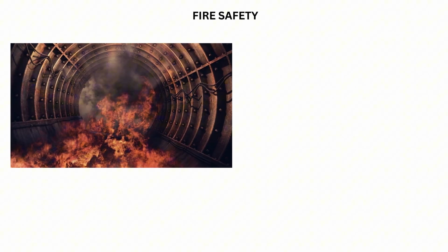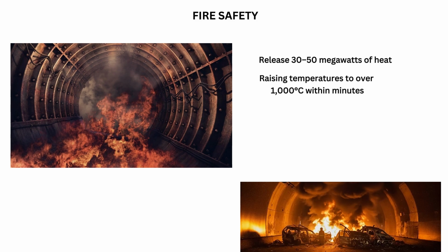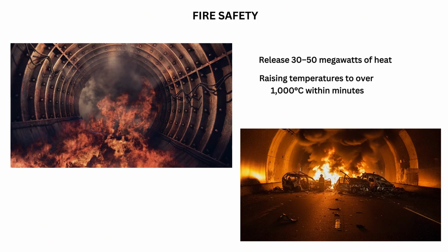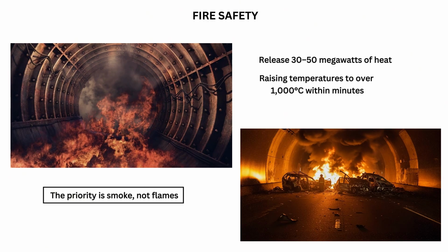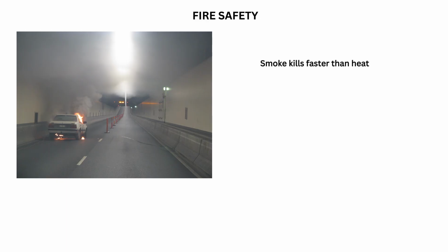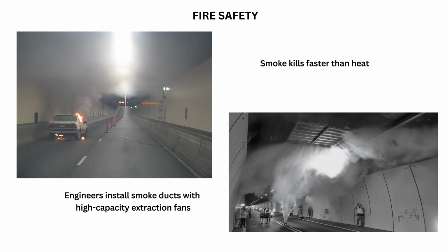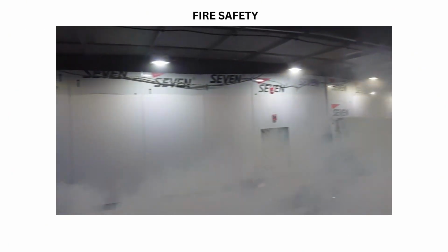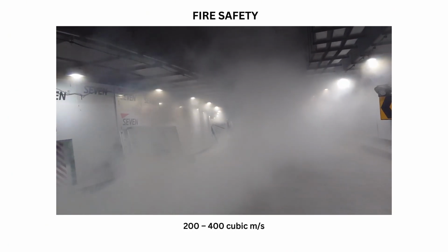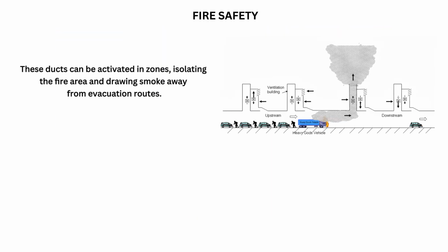Fire safety. In a fire, the rules change instantly. A truck fire in an underwater tunnel can release 30 to 50 megawatts of heat, raising temperatures to over 1,000 degrees Celsius within minutes. The priority is smoke, not flames. Smoke kills faster than heat. Engineers install smoke ducts with high-capacity extraction fans, capable of pulling smoke at rates of 200 to 400 cubic meters per second. These ducts can be activated in zones, isolating the fire area and drawing smoke away from evacuation routes.